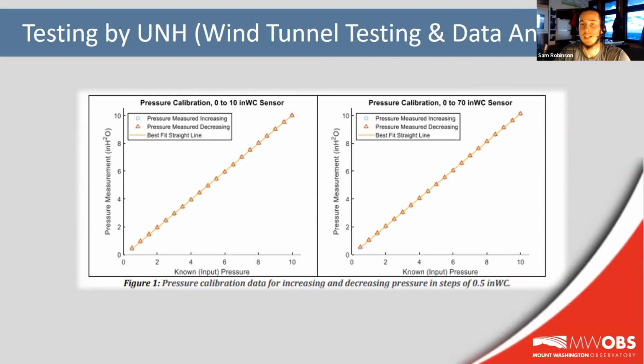And then taking a look at these figures for each sensor, it is the known input pressure of the calibration tool plotted against the actual pressure measurement that was determined by the sensor, so the actual output. And you should notice that a visual difference is basically impossible to see, but it's the 0 to 10 sensor on the left, 0 to 70 on the right, and the difference is so minimal, you can barely even tell.